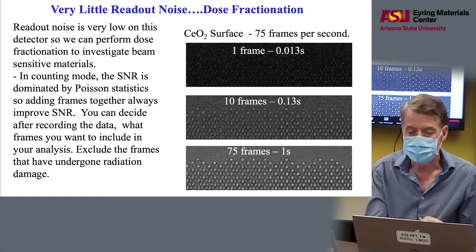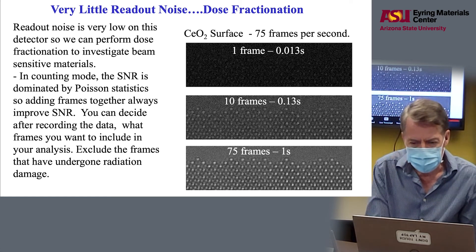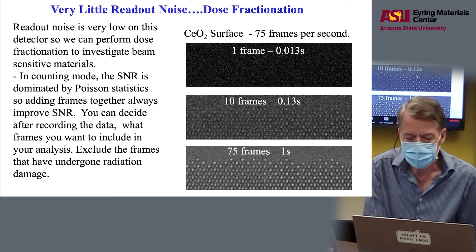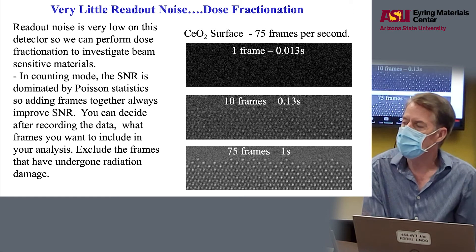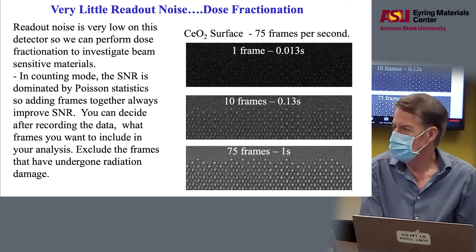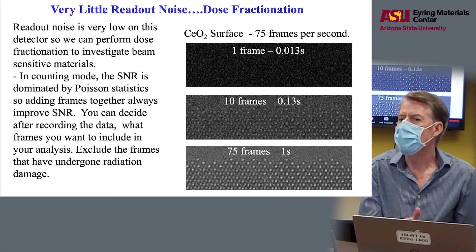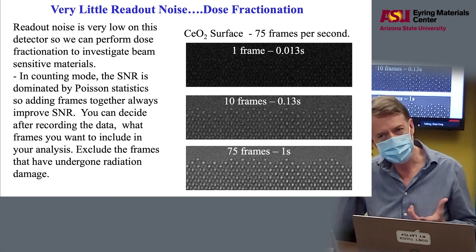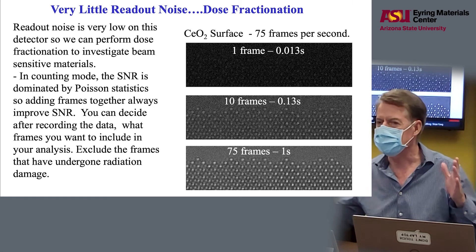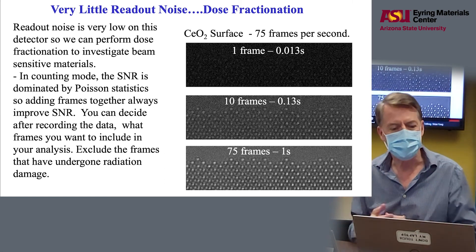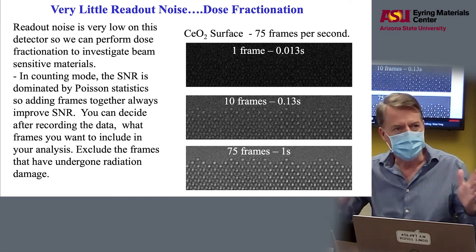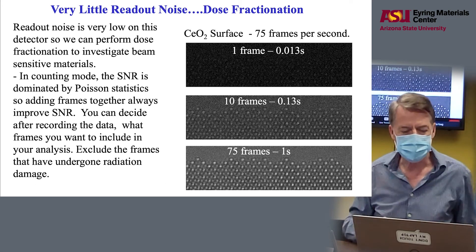This is one of the frames, and you might think that's way too noisy. So you can just take this and add 10 frames together, or add all 75 frames together to get a one-second exposure. The point is that because the noise is dominated by Poisson counting noise, you pay no penalty in terms of signal-to-noise when you do dose fractionation. With old detectors that have very large readout noise, if you divide your image into two half-second readouts, you get twice as much readout noise. The readout noise is negligible here, so we can play all sorts of games.